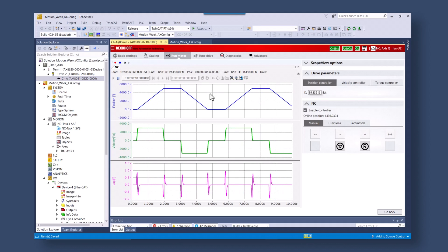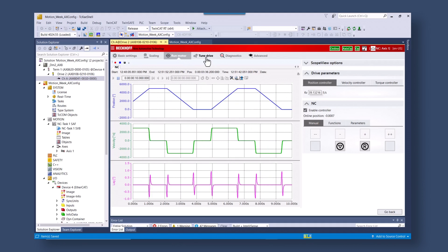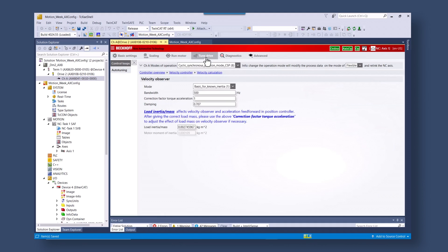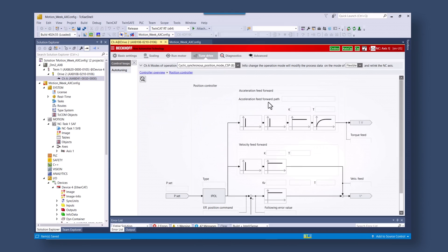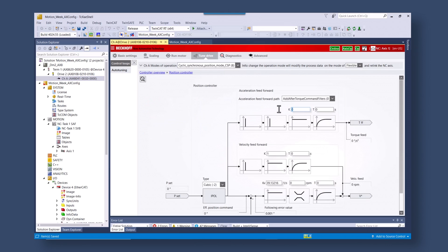There are further features that are built in. We can actually look at the inertia of the system now. You can see the 27 to 1 inertia ratio. So we know the inertia. So now the velocity observer is configured.